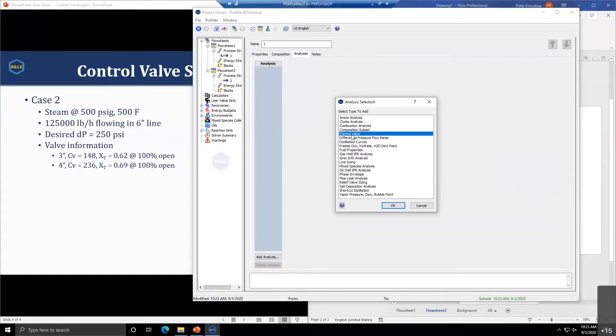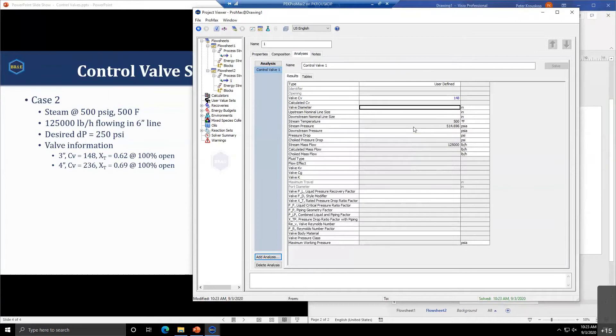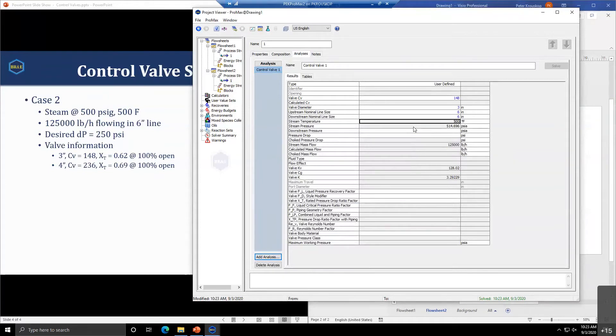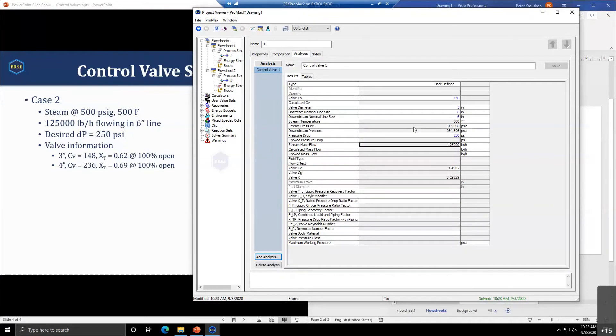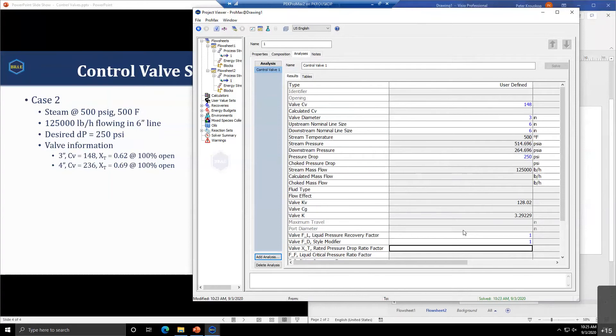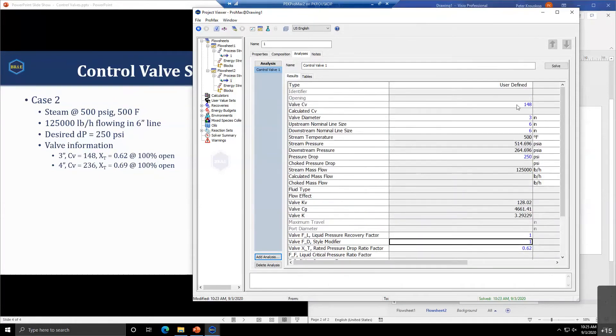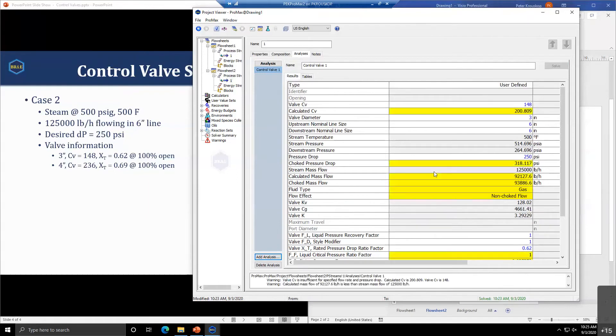We'll go to the analysis and add our control valve analysis. We'll work with the valve information we have. We're flowing in six-inch lines, but we'll try our three-inch valve first. We want a 250 pound pressure drop. Since we're dealing with vapor, the FL can be left at one, FD at one, and the XT is 0.62 for this valve.